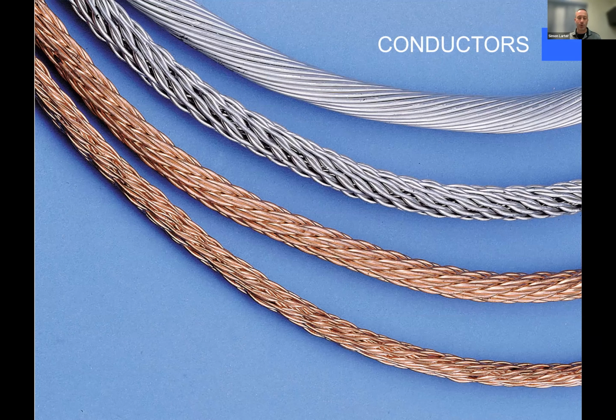So your average home, your average residence, class 1, you can use smaller cabling, you can use thinner lightning rods, less conspicuous, less conducting area, but does fine for a lower building. Once you get above that 23-meter point, now we're starting to look at capturing more lightning strikes. The building's higher, lightning strikes could be statistically more powerful.